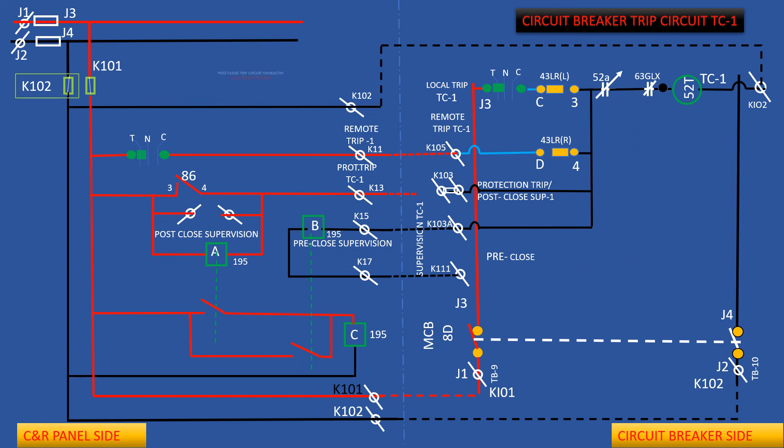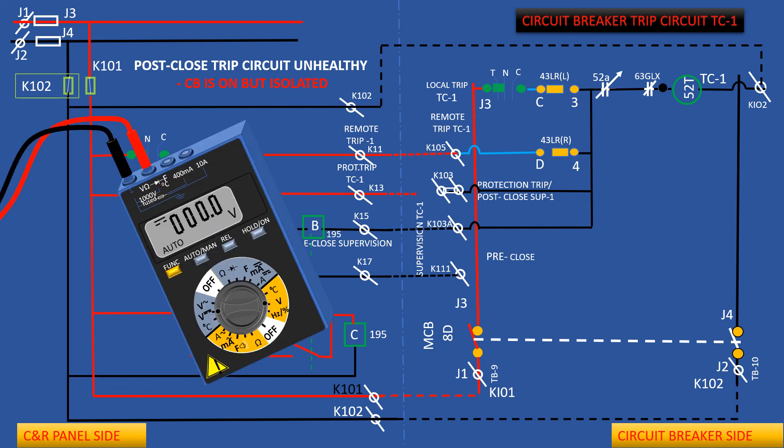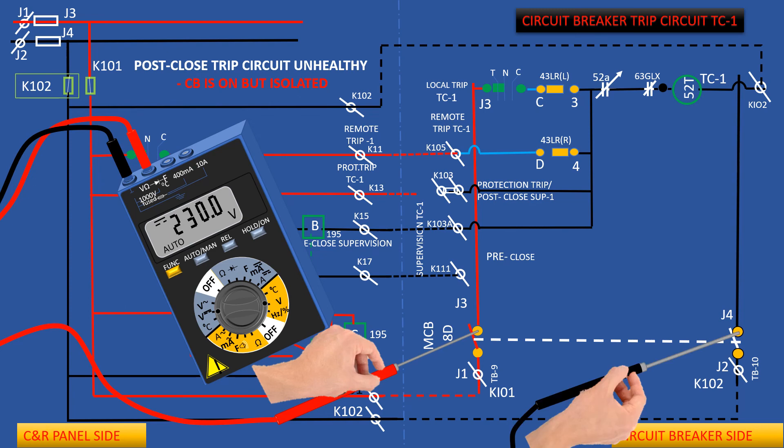Post-close trip circuit unhealthy due to fault at trip circuit. Measure voltage at each point as shown. Watch multimeter reading also.